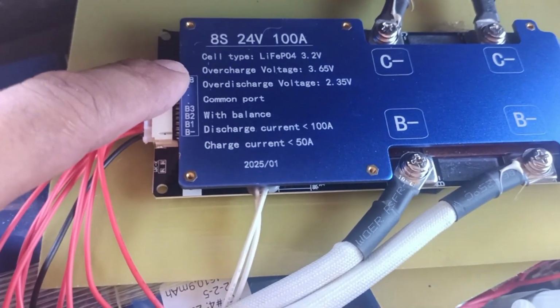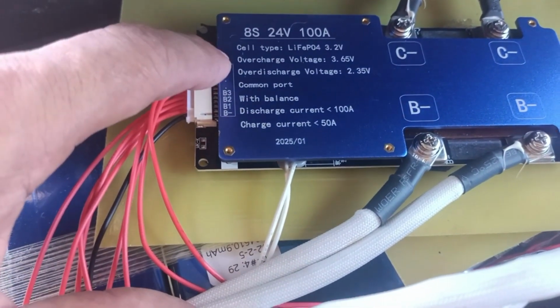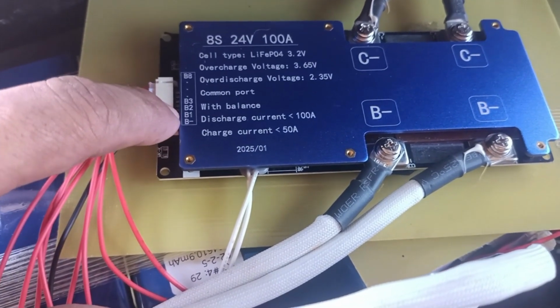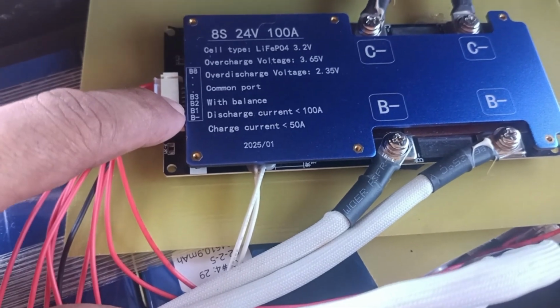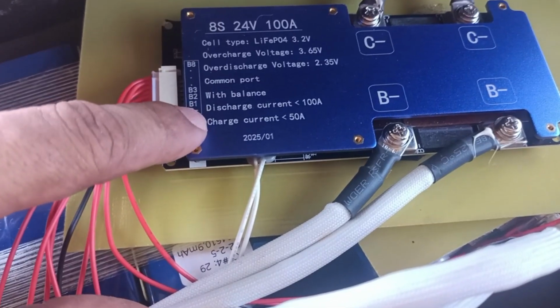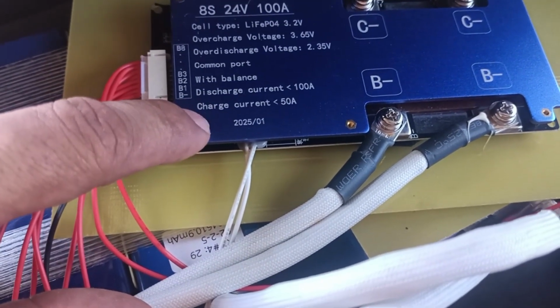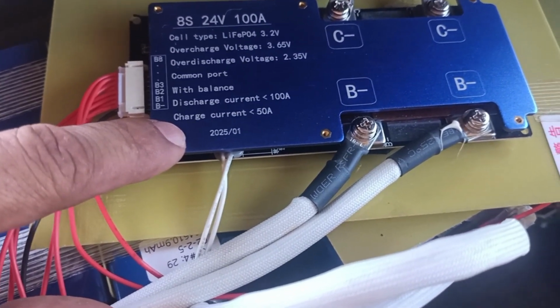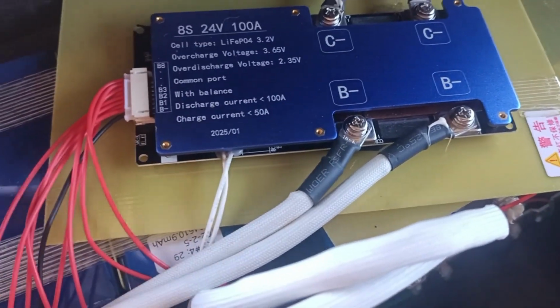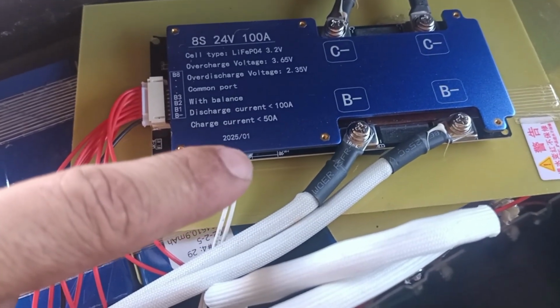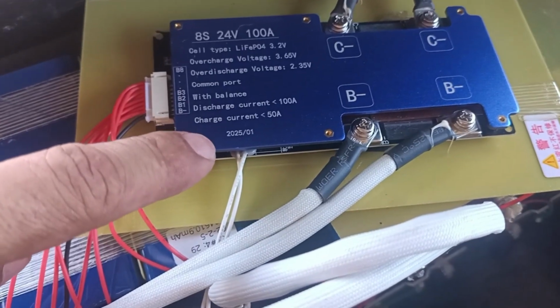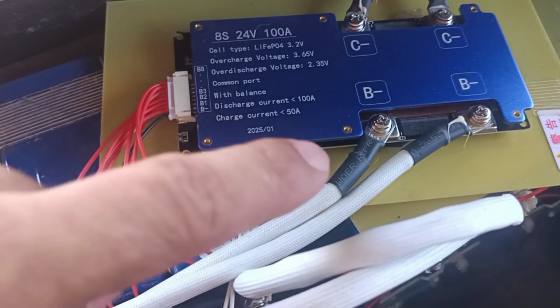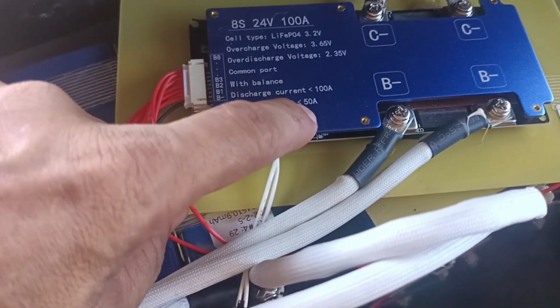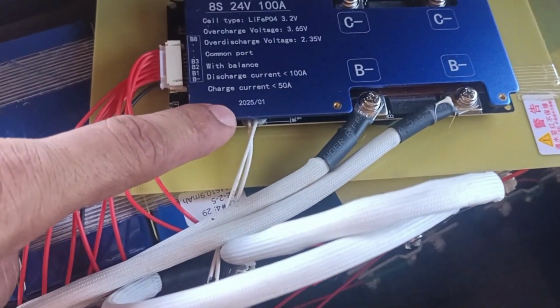So this is the BMS. The specification for this is LiFePO4. Nominal voltage 3.2, overcharge voltage 3.65, over discharge voltage is 2.35. That is depleted. So basically discharge current is less than 100 amp, and charge current is less than 50. That's what I meant by if you have 100 amp charging or discharge, one must charge it at 0.5 C. If you charge it at 1 C, which is 100 amp, this thing will start to bubble and swell and things like that. So the BMS controls the charging current even if you set that to 100 amps.